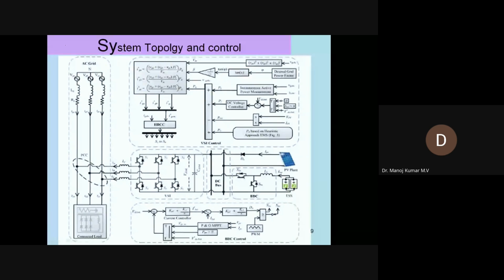If you are maintaining unity power factor at all times, which most of the inverters presently connected at the PV side of the present system do, sometimes the voltage may be high. So it is not specifically controlling the power factor, it is controlling the power factor based on the voltage which is to be maintained at the PCC. So the power factor can be controlled. That is controlled by a factor called the desired grid power factor shown here. That phi, or tan of that value, is used for computing the reference currents, given here as IGA star, IGB star, and IGC star.